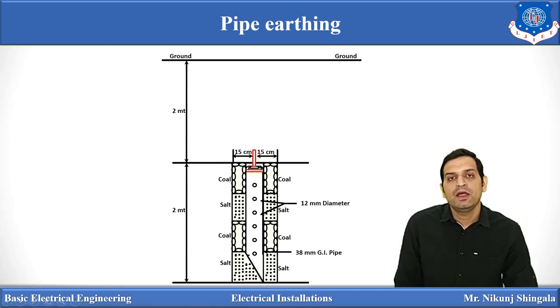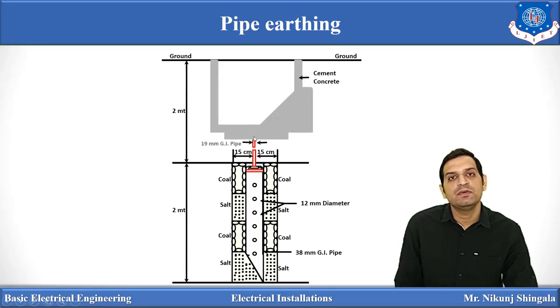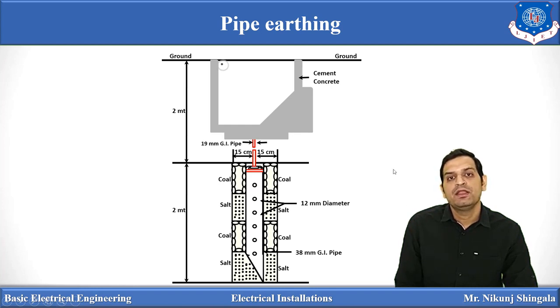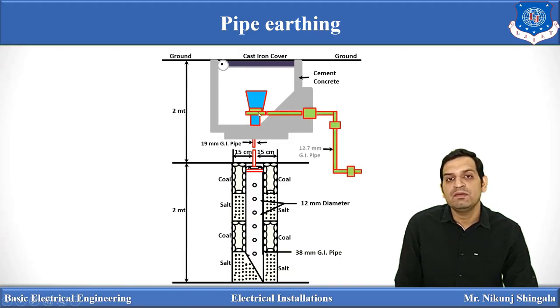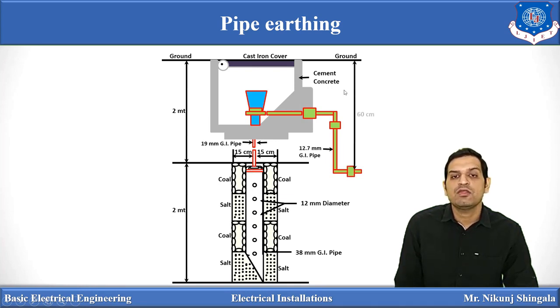Above this, cement concrete work is done, and one 19 mm GI pipe is connected with the main 38 mm GI pipe. A cast iron cover is placed over the cement concrete work for easy opening, and a funnel is provided for water pouring. A 19 mm GI pipe is also connected with a 12.7 mm GI pipe. This is the construction of the pipe earthing.